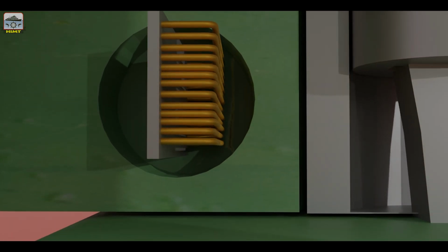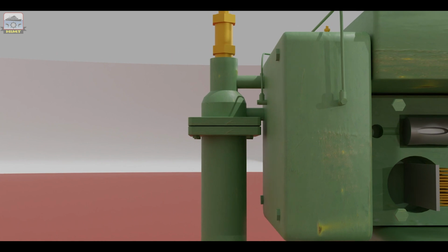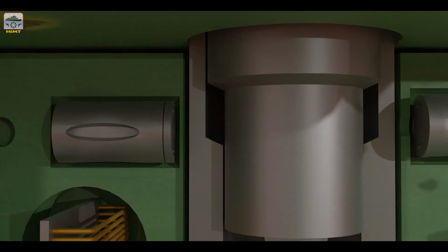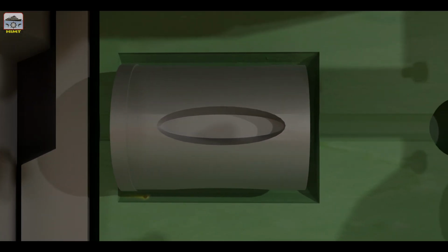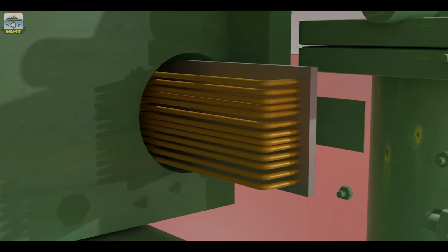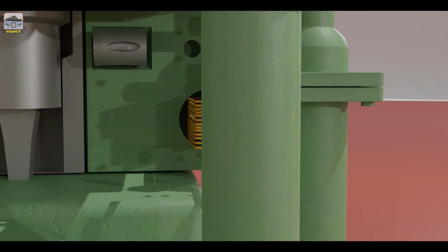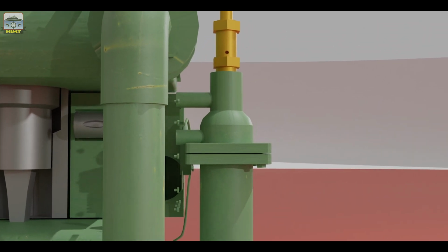The air from the first stage enters the intercooler for further compression through the second stage suction valve. The second stage discharge valve and aftercooler allow the air, after the second stage of compression, to pass through and enter the moisture and oil separator to the air receivers.